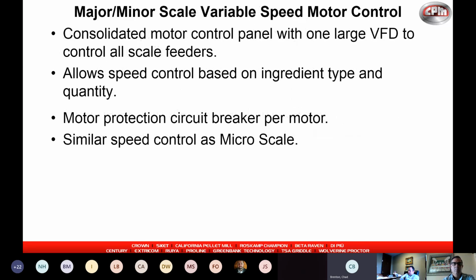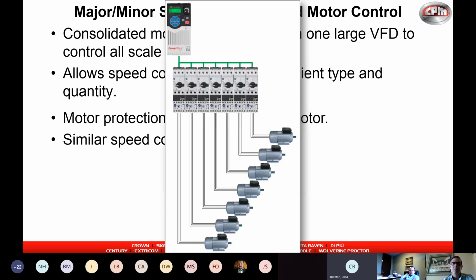A lot of our success in the past few years has been building major and minor scale feeder panels for facilities, both new and retrofits. What we do is remove all the buckets involved in a scale and design a control panel so that one VFD powers up to an infinite amount of motors really, but usually 10 to 24 motors. This way you can add VFD control to your batching system without having to buy a VFD for every screw.